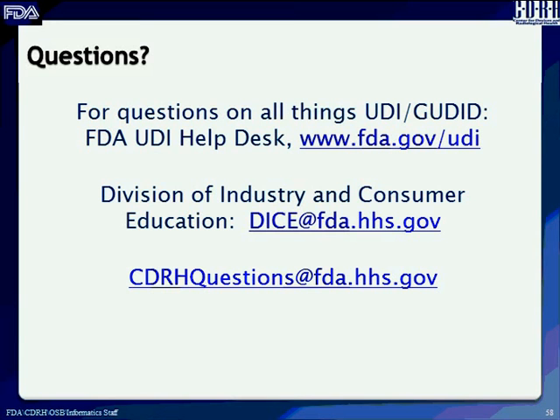Okay, so just to confirm, I got that right. You said EMDR is not required to submit the UDI until August 2015. No, I did not say that. We're looking at reasonable timeframes for that, and that's why I asked that you let us know about that, and then our MDR policy group is coming up with a policy on that, in recognition that the EMDR systems are not fully capable of accepting the UDIs. So we're asking companies, particularly Class 3 companies, to notify us because of the September 24th deadline. Okay, thank you.